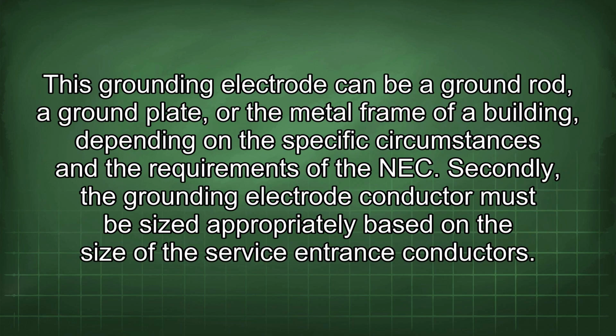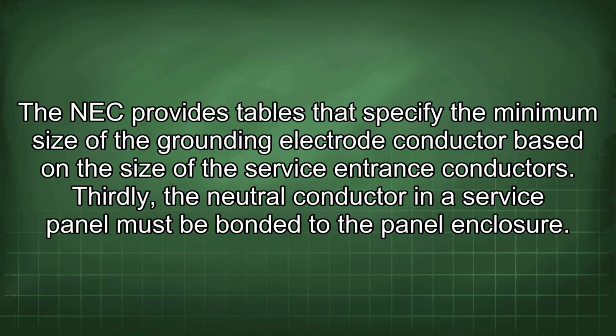This grounding electrode can be a ground rod, a ground plate, or the metal frame of a building, depending on the specific circumstances and the requirements of the NEC. Secondly, the grounding electrode conductor must be sized appropriately based on the size of the service entrance conductors. The NEC provides tables that specify the minimum size of the grounding electrode conductor based on the size of the service entrance conductors. Thirdly, the neutral conductor in this service panel must be bonded to the panel enclosure.